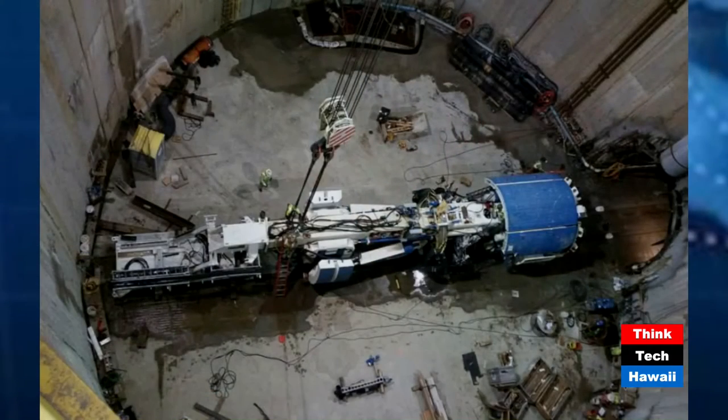The tunnel runs under mountains — it's a lot of pressure. The elevation grade is about a 35-foot vertical drop from the Kaneohe site to the Kailua site, which is an engineered hydraulic function — the water can't go too fast. The tunnel stores about 8 million gallons so Lori's plant operators can meter that into the plant, staying within their guidelines. Treating all 8 million gallons in one day wouldn't happen — it would be over a span of a number of days.